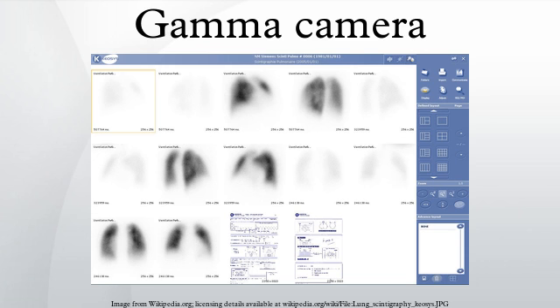Spatial resolution decreases rapidly at increasing distances from the camera face. This limits the spatial accuracy of the computer image; it is a fuzzy image made up of many dots of detected but not precisely located scintillation.